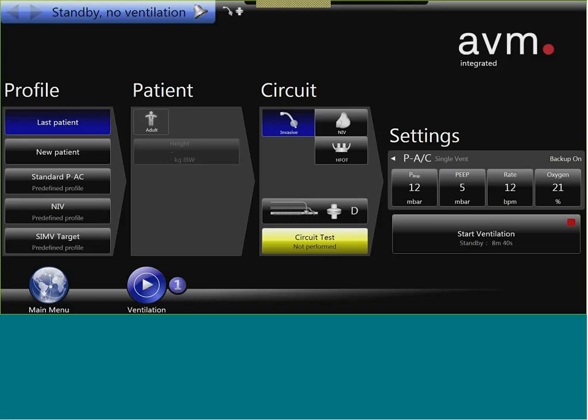So if some fluid or water comes into that, your ventilator is broken, and you have to replace a $2,500 inspiratory valve. So that's the reason to put on a 50-cent filter just to protect the ventilator.